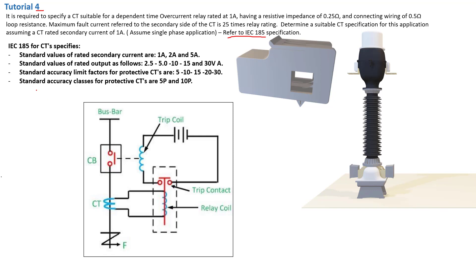The next standard we have is the accuracy class. We have two of them: 5P and 10P. These represent the margins of error. So if you say 1,000 times 10, and it's a 5P class, it will be within plus or minus 5%. If it's a 10P class, it will be within plus or minus 10% of your CT value. That's basically what these standard values mean, and you must be mindful of this when selecting your current transformer.